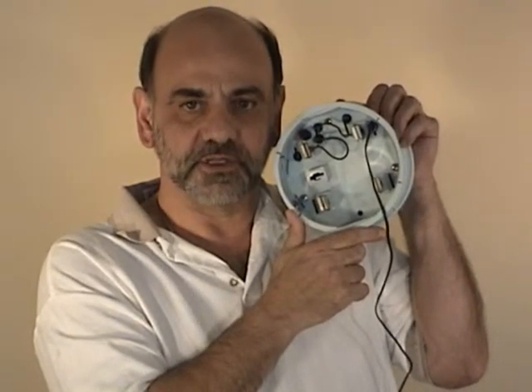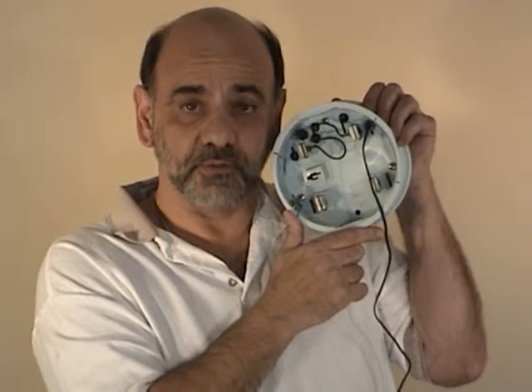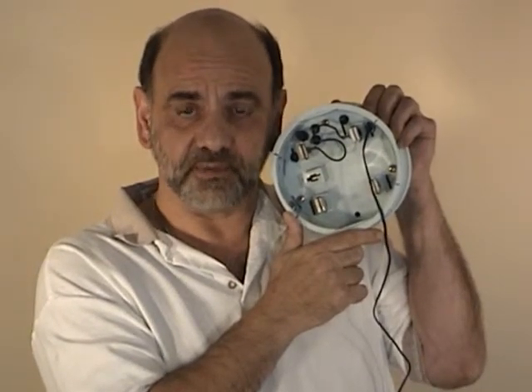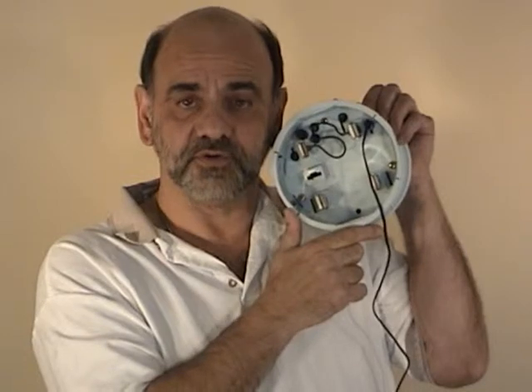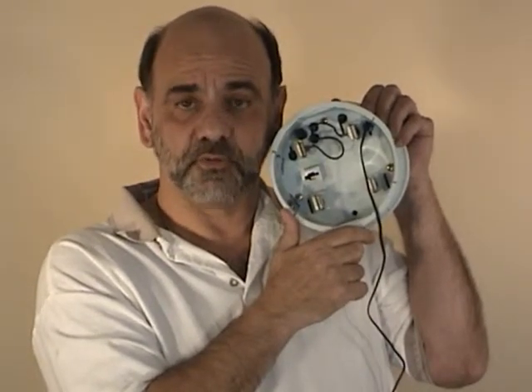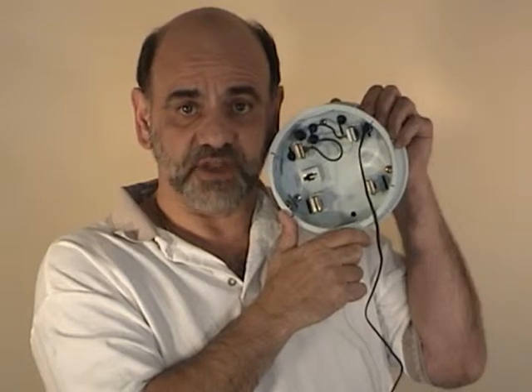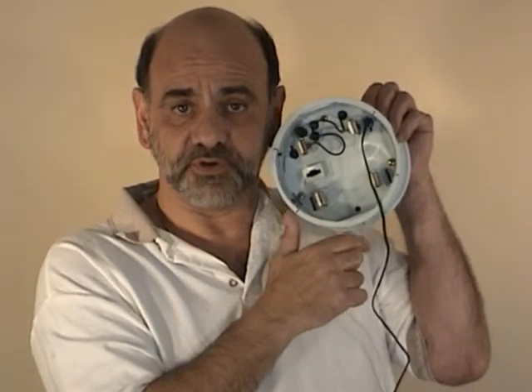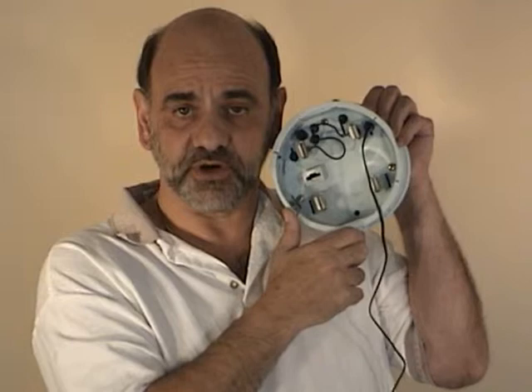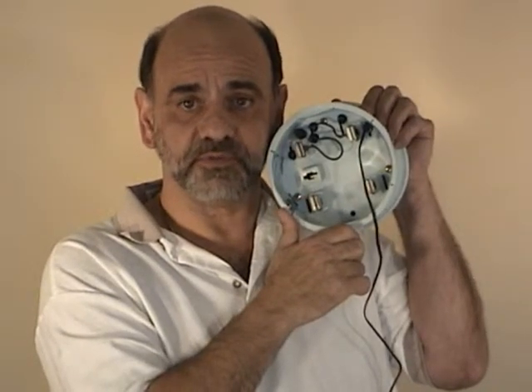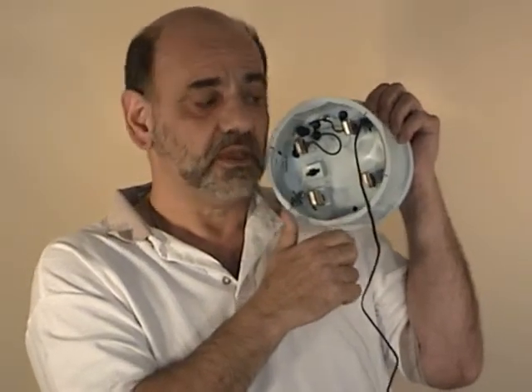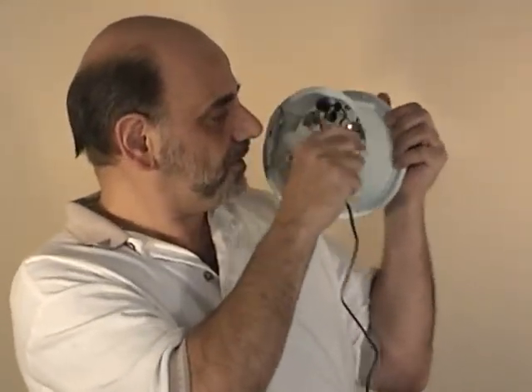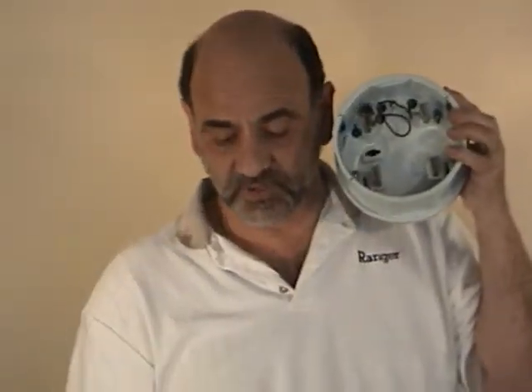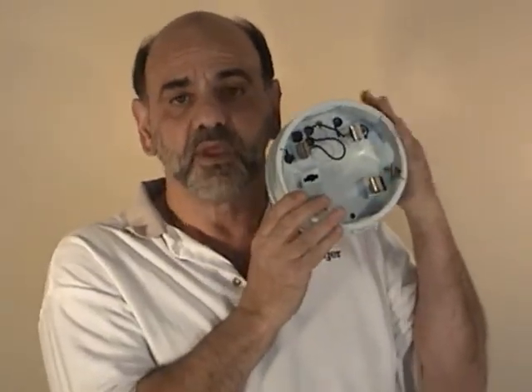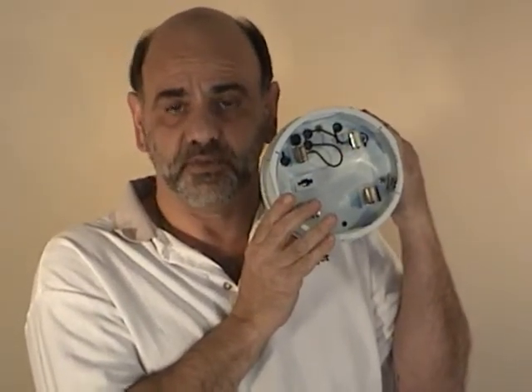Now remember, we want to be very clear that the unit comes standard from the factory with a 7-day recording time period and set points set at 126 volts and 114 volts. But you can change those set points if you want to, because that's where you get your warning LED indication. You can change them to whatever you like, and you can change the time recording period from 7 days to whatever you like also. Now, I'm going to unplug the wall charger from the unit, because we want to talk about some of the different setups that come in the unit. There's 8 different setups that come in the unit.